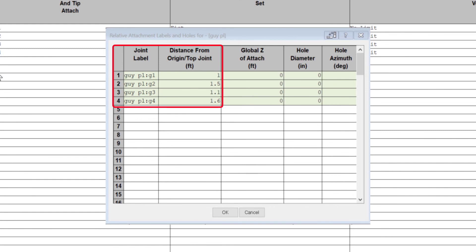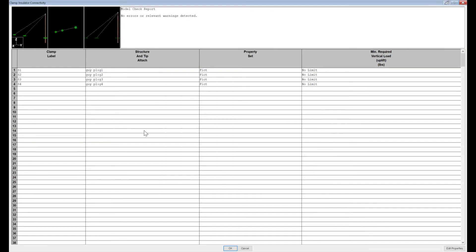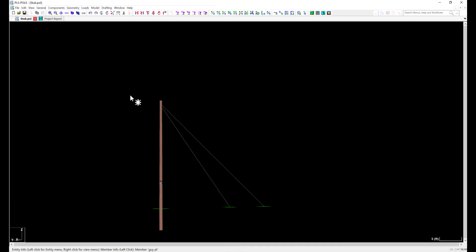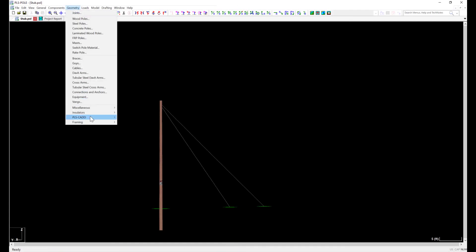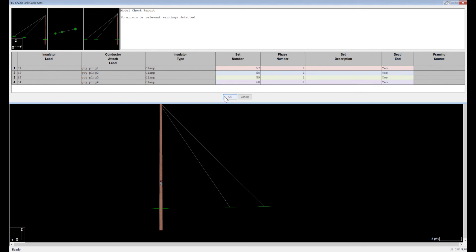This will be close enough to mimic a single attachment point without getting the attachment point location warning. Again, I navigate to Geometry, PLS-CADD, Insulator Link to verify that I have my insulators linked for PLS-CADD use. Since I have 4 clamps to link, I used 57 through 60 for set numbers with phases of 1 for all.